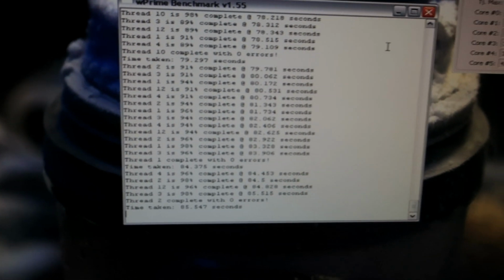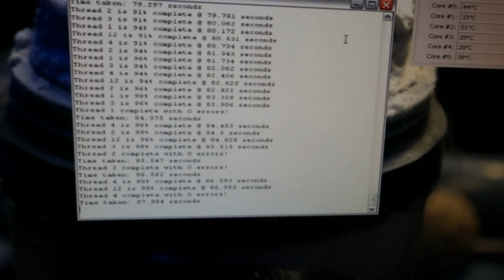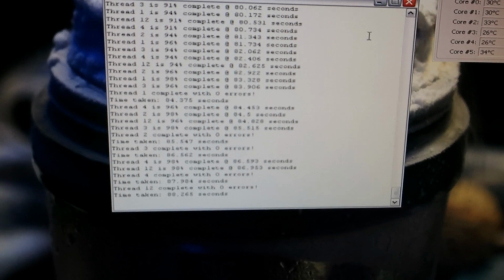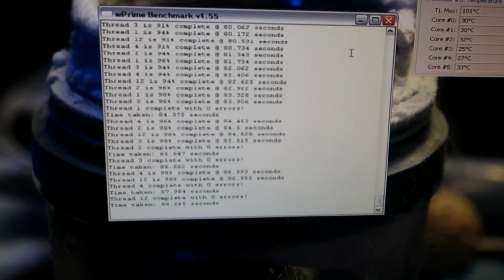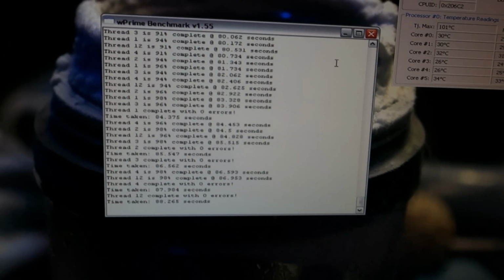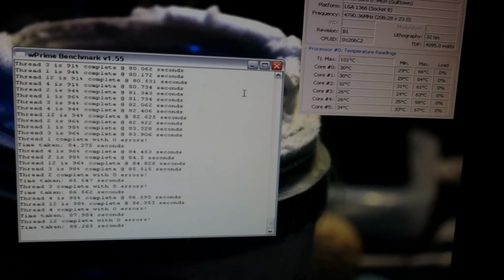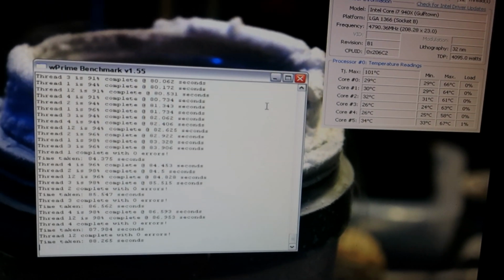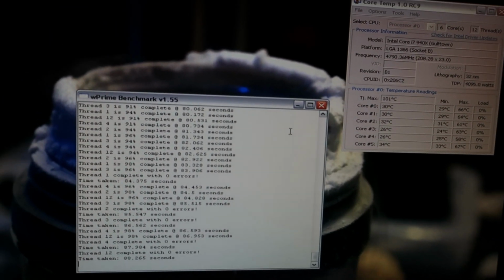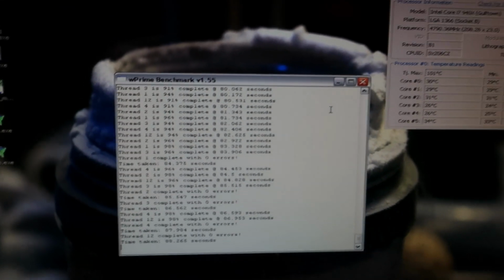The cores are too different from each other, so it will just lock at 100%. So yeah, there were some errors, but the measured value under load was 1.406, so it's very on the edge. 1.41 to 1.415 should pass, so it's a very nice result.